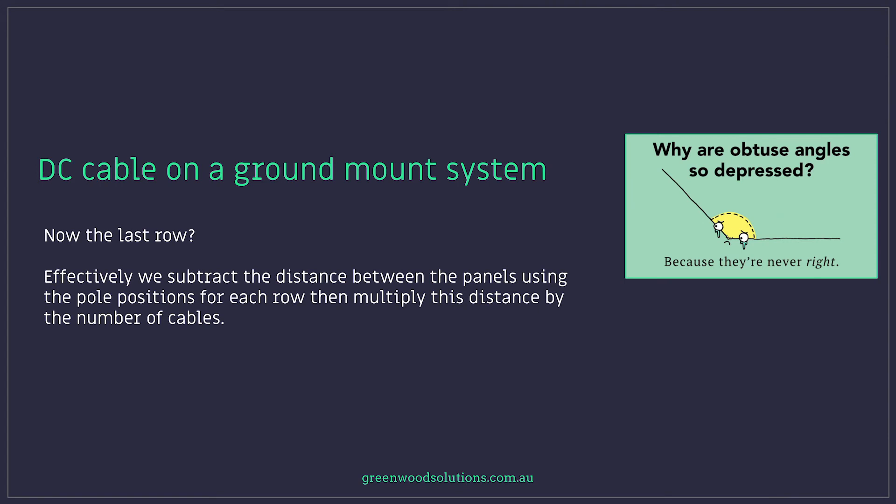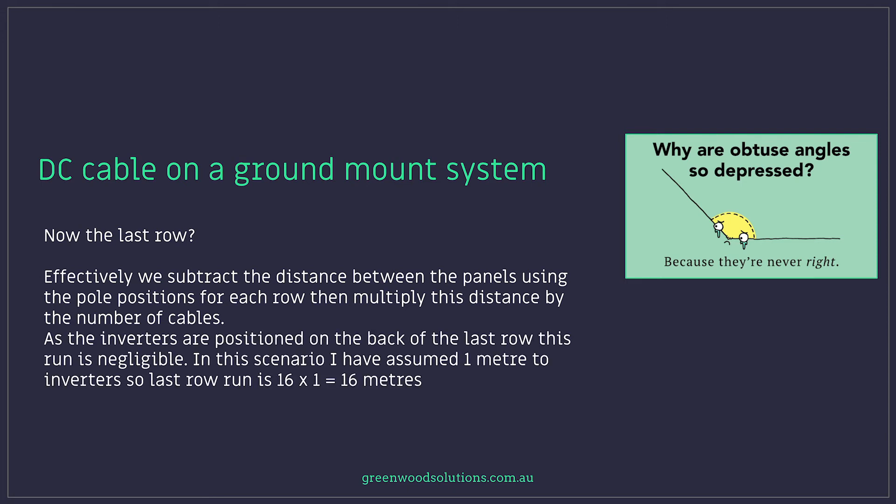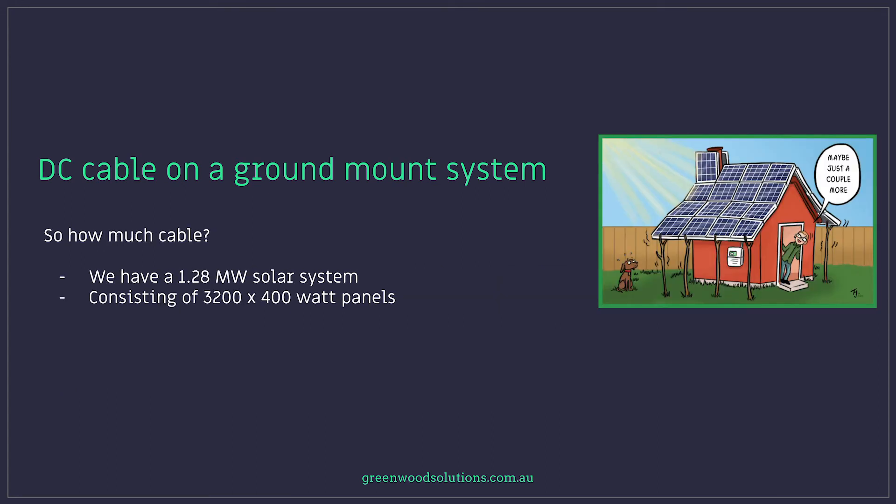Effectively, we subtract the distance between the panels using the pole positions for each row, then multiply this distance by the number of cables. As inverters are positioned on the back of the last row, this run is negligible. In this scenario, I have assumed one metre to inverters, so the last row run is 16 times one equals 16 metres.